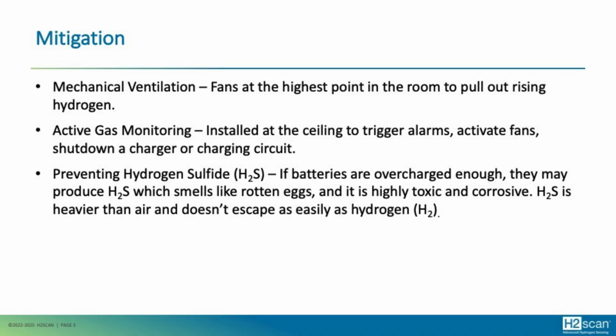Codes and standards have a requirement for mitigating hydrogen. The most popular, of course, is mechanical ventilation. This is where we install fans towards the ceiling and pull air through a room and evacuate the hydrogen that way. Interestingly enough, unless you have redundancy in your mechanical ventilation or another plan to mitigate any kind of failure with those mechanical devices, oftentimes the authority having jurisdiction wants you to have some other form of backup in case you do have a ventilation issue.